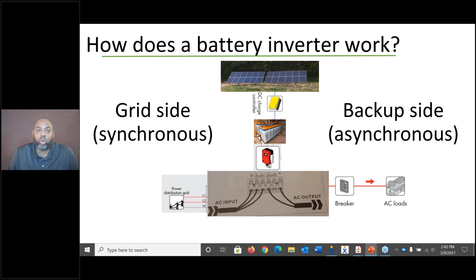So the next design principle that I want to go to, and this is probably the most important, and this all ties back to the first point: increasing the inverter size means increasing the minimum battery size. So a simple rule of thumb, put this in your memory banks: the minimum battery size is twice the inverter size. And the reason why we say twice is the 2-hour discharge principle that I showed you in rule number 1. So for simple math, if you have a 5 kW inverter, you would multiply that by 2. 5 times 2 equals 10. So the minimum battery size you would need is essentially 10 kWh.